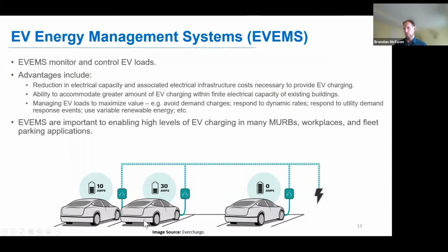And basically, if only one vehicle is plugged in and charging, it could take the full capacity of this branch circuit. So in this case, the circuit is 40 amps, and it could take that full 40 amps and charge relatively quickly. But if multiple vehicles are plugged in and charging simultaneously, the charging stations communicate with one another, and they throttle down how much charging they're providing so that they don't exceed the capacity of that circuit and trip the breaker. So when you are sharing power in that way, you are charging at a slower rate for that period of time. But for a lot of applications, notably residential charging, that's just fine. A certain amount of sharing is okay.